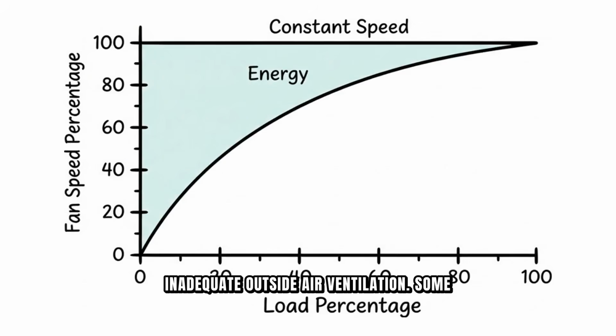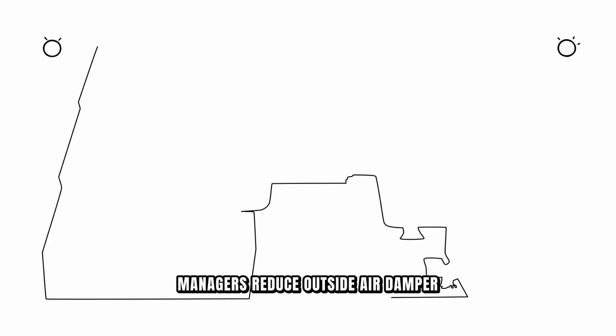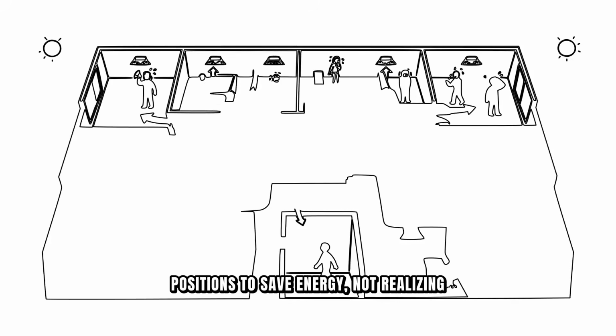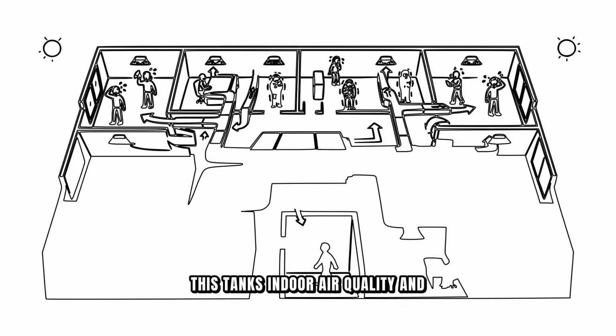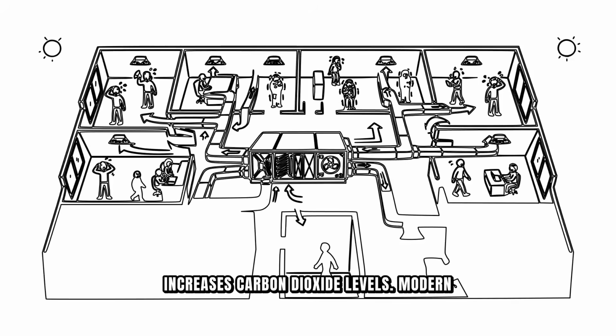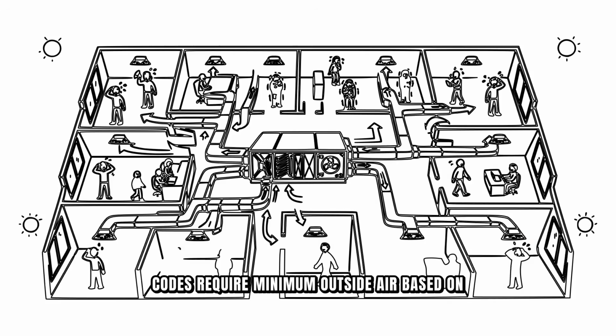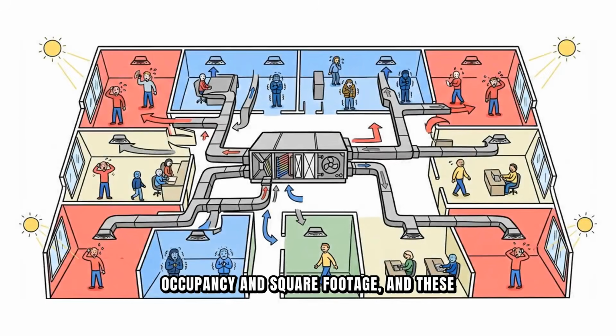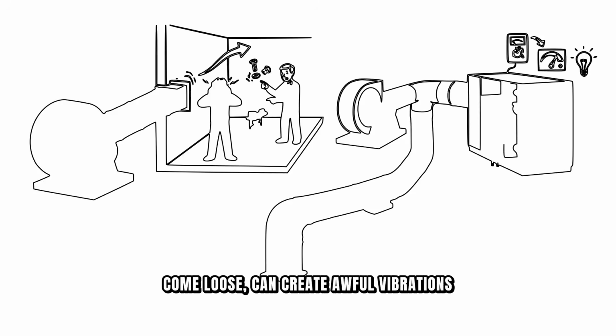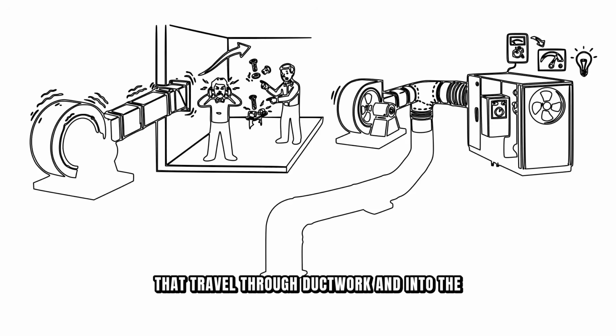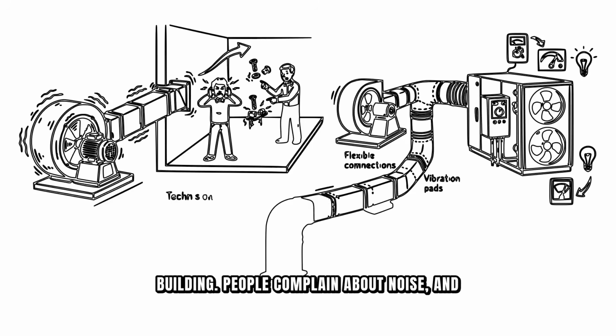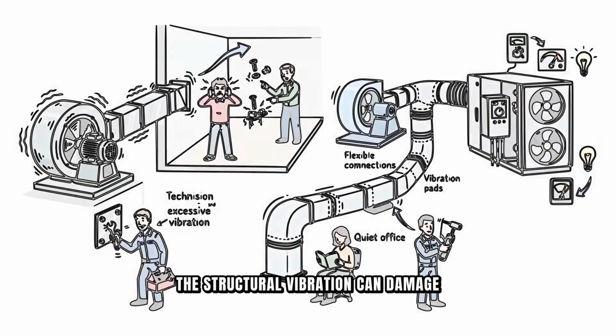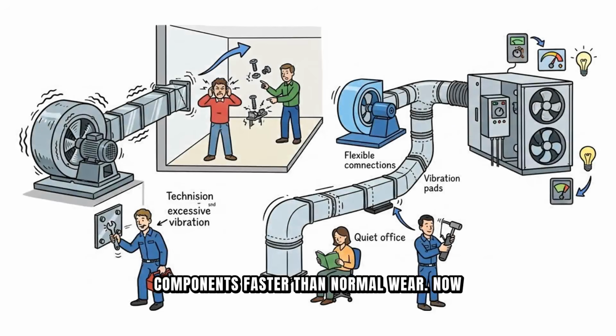Seventh is inadequate outside air ventilation. Some facility managers reduce outside air damper positions to save energy, not realizing this tanks indoor air quality and increases carbon dioxide levels. Modern codes require minimum outside air based on occupancy and square footage, and these requirements exist for health reasons. Eighth is vibration and noise. A fan out of balance or mounting bolts that have come loose can create awful vibrations that travel through ductwork and into the building. People complain about noise, and the structural vibration can damage components faster than normal wear.